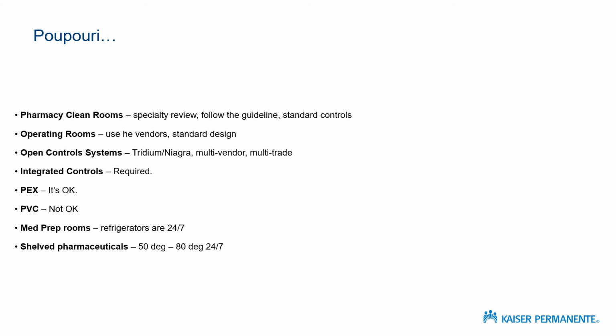The med prep rooms have become a problem for us in our design. Those refrigerators are 24/7, and they tend to ruin any type of energy optimization sequence that you can imagine. And so we always check those on our project to make sure that they're dealt with in a way that lets the rest of the systems function. The shelved pharmaceuticals is also a kind of a unique issue for Kaiser. We tend to have medical office buildings where we have outpatient pharmacies that don't stay open 24/7 like a retail pharmacy would. The medical office building will be open 9 to 5 during the week and then closed on the weekend. We do need to maintain those shelved pharmaceutical spaces between 50 degrees and 80 degrees 24/7. And so we need to have a design in place to do that.